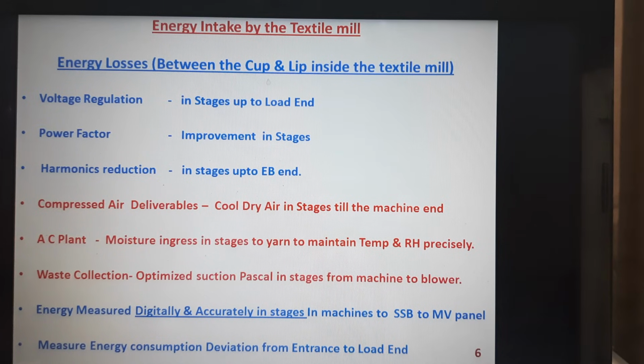Thanks to Bureau of Energy Efficiency, a lot of power factor discussions have already taken place, guidelines have been given to the energy auditors and energy managers that from the equipment side it is maintained around 0.8 by the load and compensation capacitors, around 0.9 at the SSB and around 0.98 at the EB incoming side. The harmonics reduction also at the equipment end, let us try to have the line reactance chokes at all the VFDs. See to it that the harmonics, say around 30%, is reduced to 15%, half the harmonics is arrested at the VFD input itself, and then at the SSB let it get detuned, and at the powerhouse see to it that at the incoming it is less than 10%, what is stipulated by the existing EB norms as such.